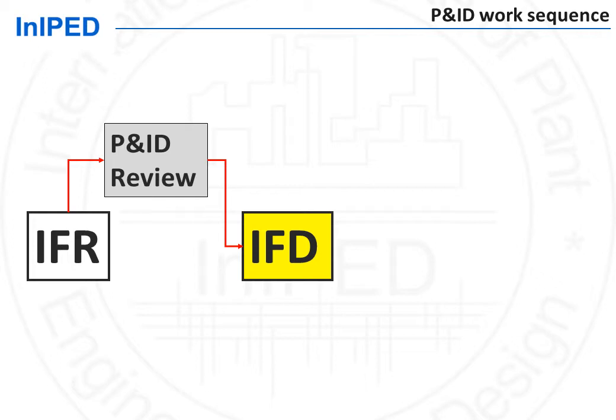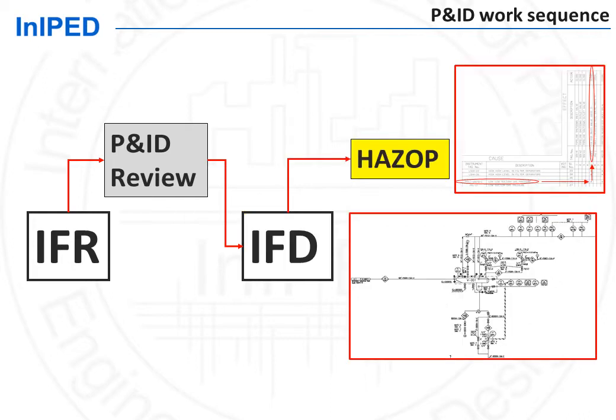Once the review has been held and the changes have been incorporated in the P&IDs, they are reissued in the revision called IFD, issued for design. But this is not the final issue of the P&IDs. Indeed, P&IDs must be subject to an audit called HAZOP. The HAZOP, Hazard and Operability Study, is an audit of the process shutdown system designed by process. It ensures that safeguards have been provided against all possible deviations of process parameters. If such safeguards are found to be missing, then an action is recorded in the HAZOP report for the engineer to add such a safeguard.